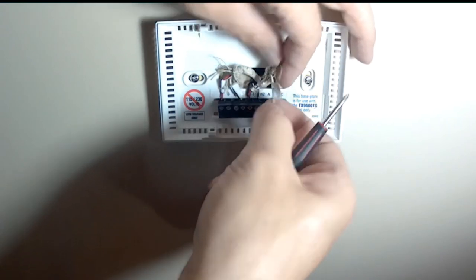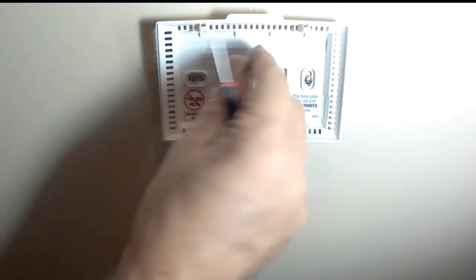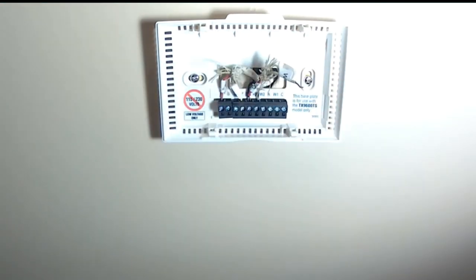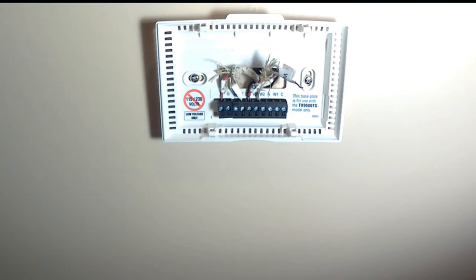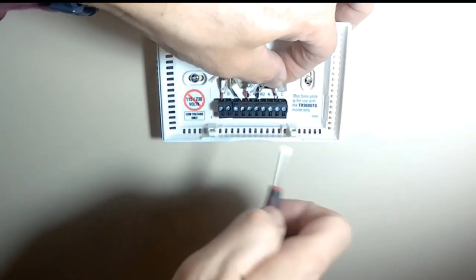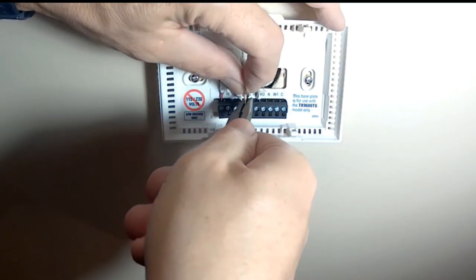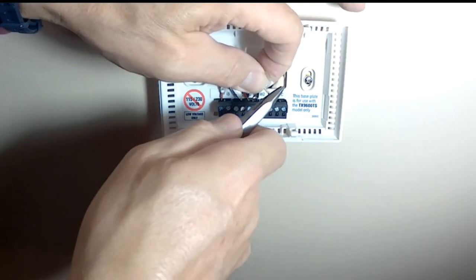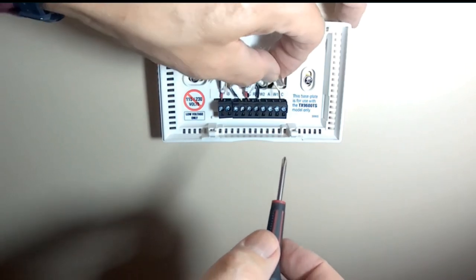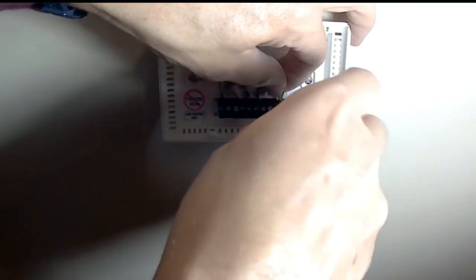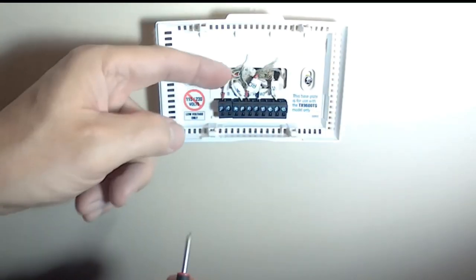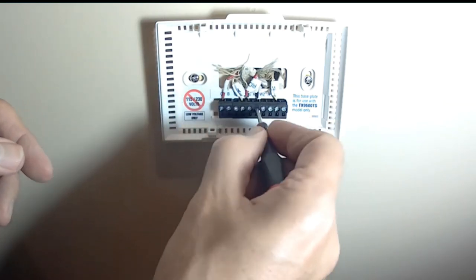And the last one we have is a W. W goes, I don't know where it goes. W1, W2. This is where reading the instructions probably could help. I have to read the instructions. I hate doing that. Oh that's for a one or two stage heater. So according to this if you only have a one stage heater and one stage cooling, you just go to W1. That's all I got. I just go to W1. Simple. Let's just go to W1 then. W is W1. Screw backed out. Got a little bent end over here. It won't go in. So I got to flatten it out. Straighten it out. Solid wire, not stranded. Put that in there. Tighten that up. Tuck those wires into the hole. Nice and flush. Make sure they're all tight.